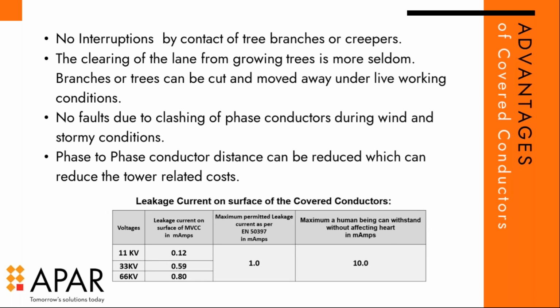Phase-to-phase conductor distance can be reduced—I'm talking in the Indian context here. Our approving authority has not yet come out with clear-cut guidelines on how much the phase-to-phase conductor distance should be reduced, but we have already tested it up to 50 mm, and we can do that without any problems.